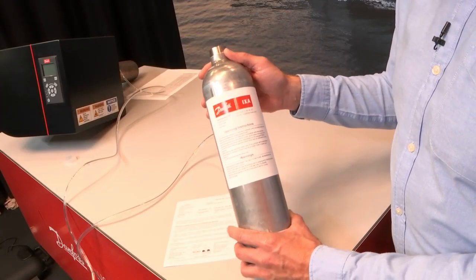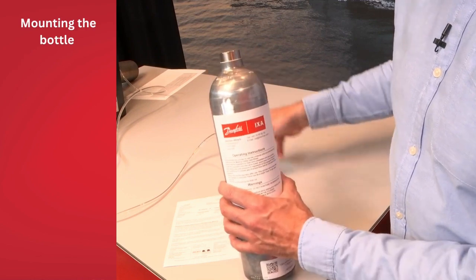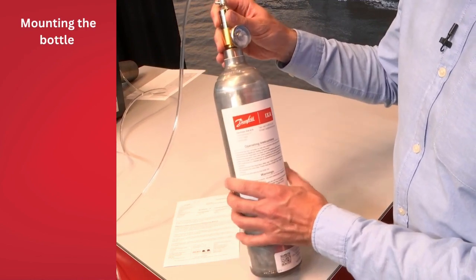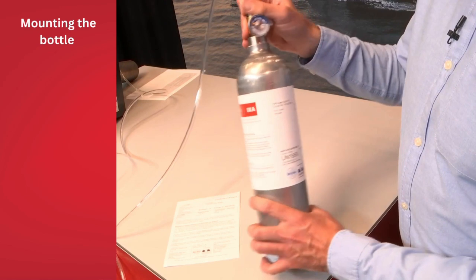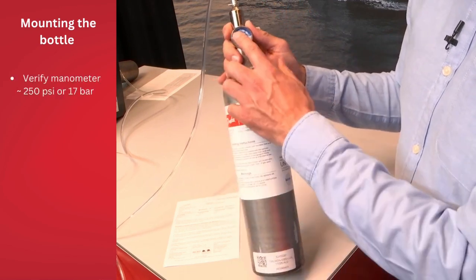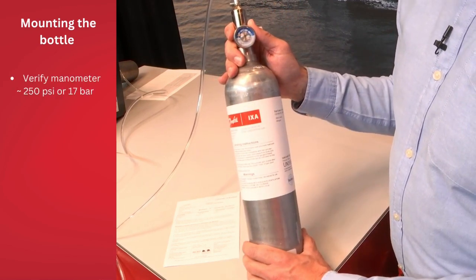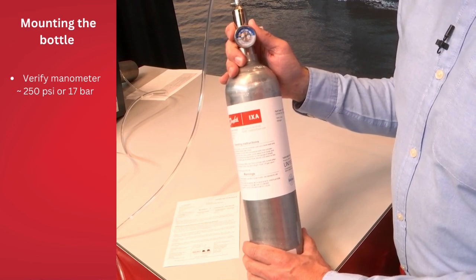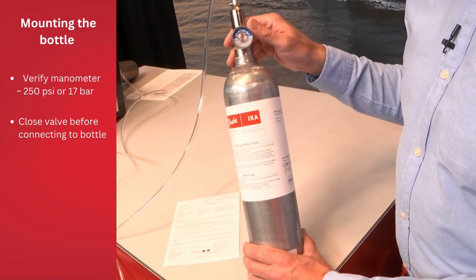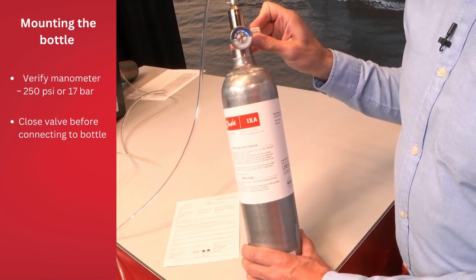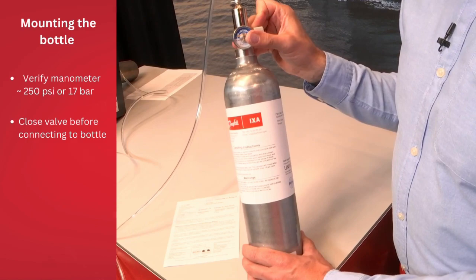Now you are ready to use the span gas bottle and connect the valve and manometer onto this. When using the bottle, please make sure that you have at least 250 psi or around 17 bar before starting the calibration. The valve of course needs to be closed before connecting all this to the bottle.